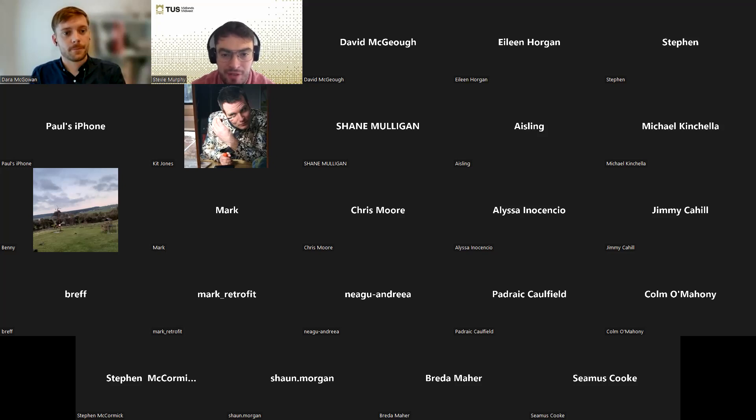Last question: I've heard decentralised MVHR is not great. Can you clarify when and where it is best used? There are pros and cons to all systems, but we use decentralised MVHR in domestic, non-domestic, new build, and retrofit — it just depends on the house type, the situation, and the scenarios. It really finds its niche in retrofits, for obvious reasons: if there's no room for ducting, or in projects where people don't want to drop ceilings or run ductwork throughout the building. It's also quite common in residential developments from a cost perspective, as it can save costs in terms of having to drop ceilings. That's why we carry both centralised and decentralised in our range.